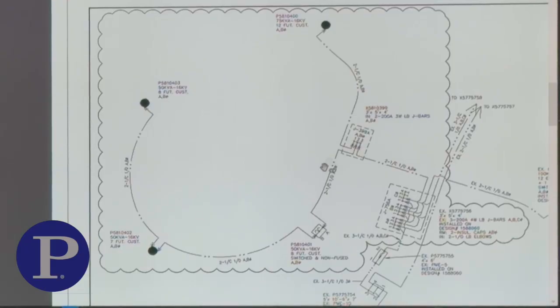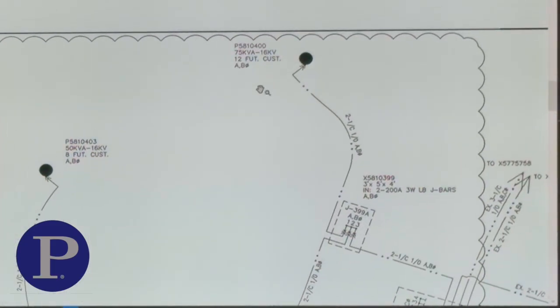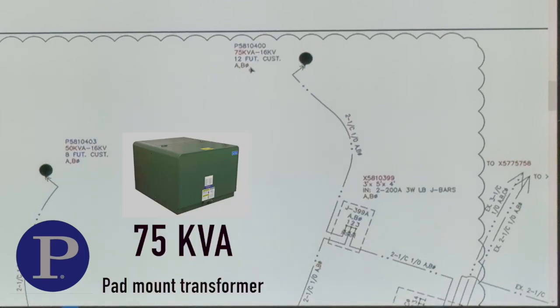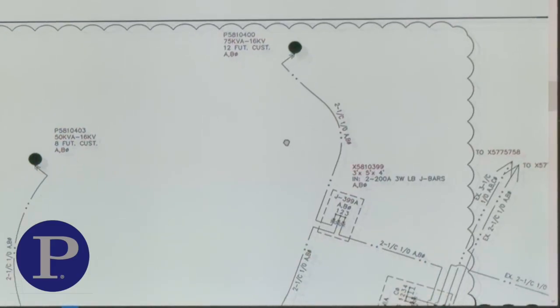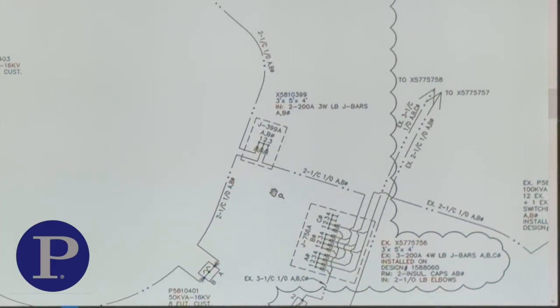This pull box here will feed this transformer, which will daisy chain to this one, and it'll end on this transformer. In addition to that, a single line will show you this is a 75 kVA transformer that's going to be installed in this spot. 16 kV tells me that I've got two phases here, A and B, which gives us our 16 kV.